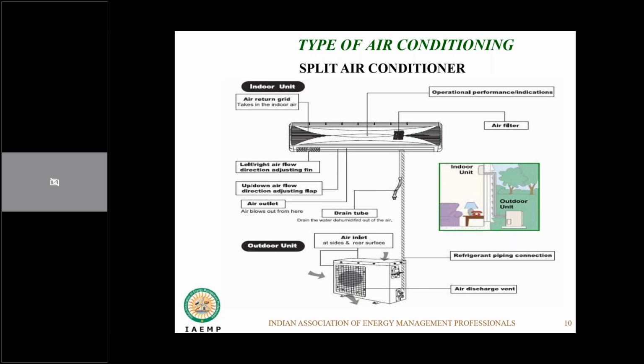We could now increase the width of the indoor unit, so it improved the heat transfer surface area, and with that we could reduce the airflow requirements and the speed of the fan, so that we could make this unit more silent and more elegant to look at. Now we have, of course, multiple models of indoor unit available, which can go with the interior layout of your facility. You have high wall mounted units, cassette units, floor mounted units and all that. All these units have a common point. You need to have a drain connection to this unit, so that whatever condensate happens by virtue of cooling has to be drained out.